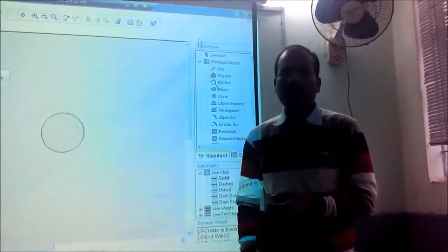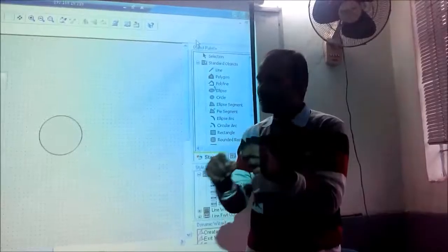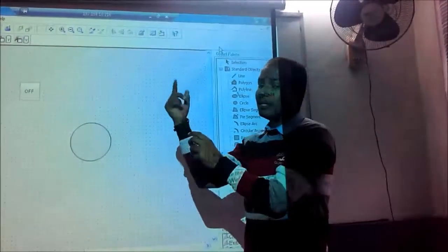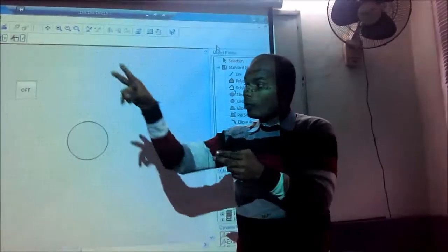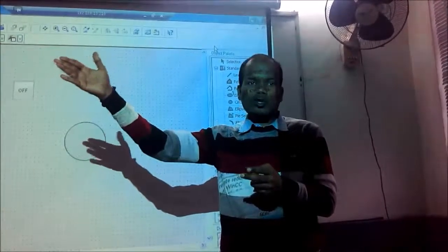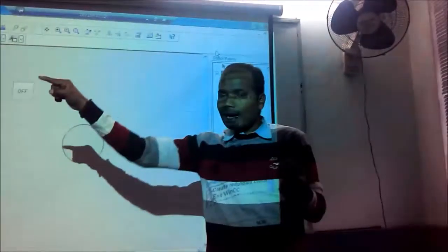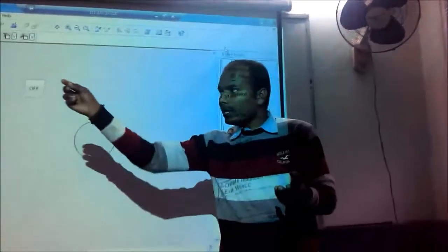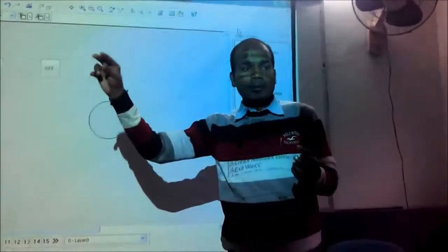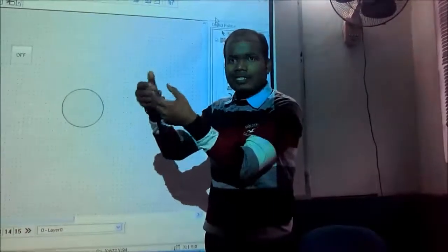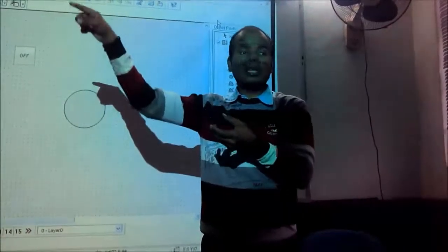Because to get feedback, what is our expectation? Our expectation is that if the LED doesn't work, we need to have an output here showing that the LED is not glowing. But if I do this task using one tag, then that LED goes off, but this output will not go off. Why? Because the tag will be enabled. But the reasons for the LED going off might be many more. Like if the LED is there but the wire is not properly connected, so far as the command is concerned, that is being sent from here to there irrespective, but that command is not reaching the output. So the indication will be glowing, but the actual output is not glowing. So in this conception we have a kind of misconception, right?